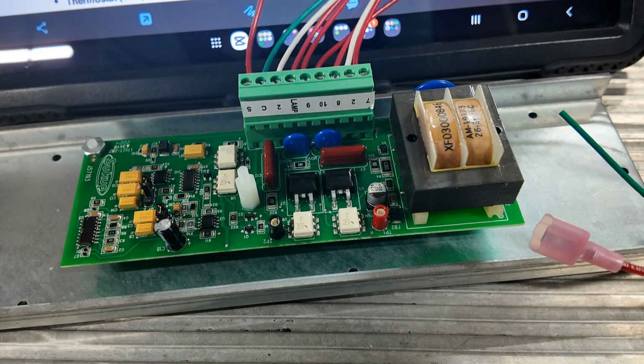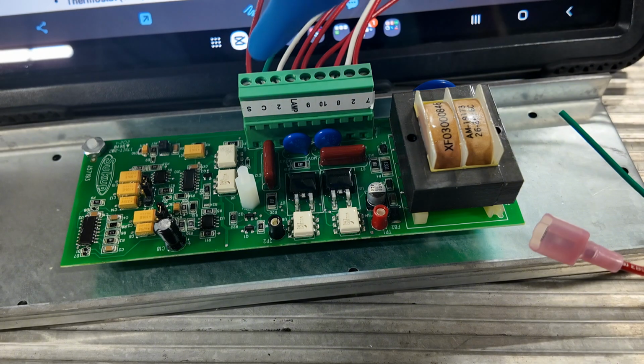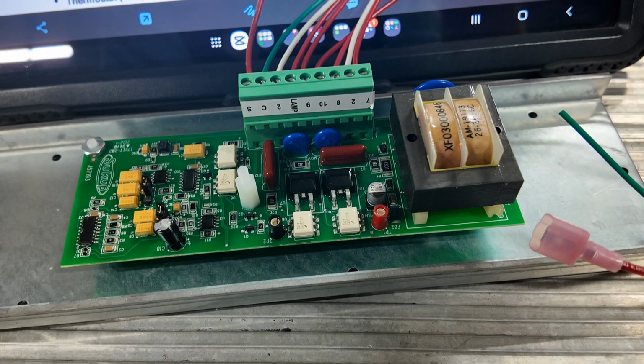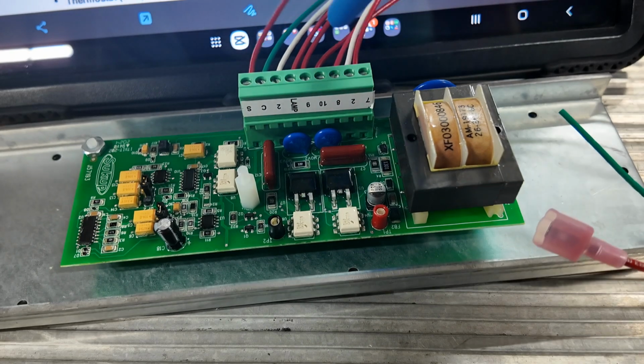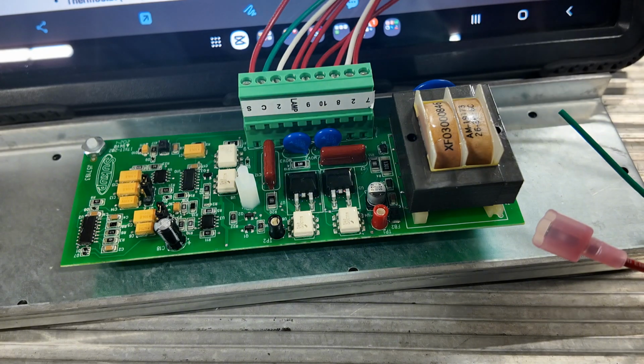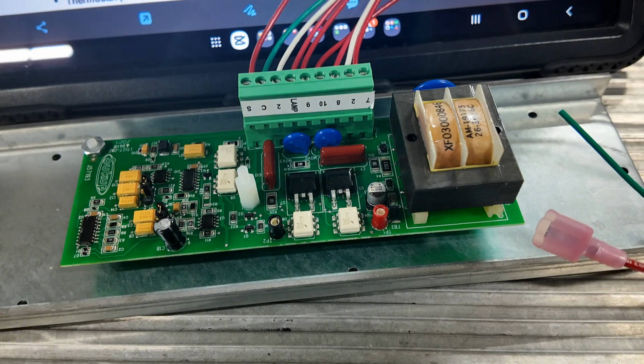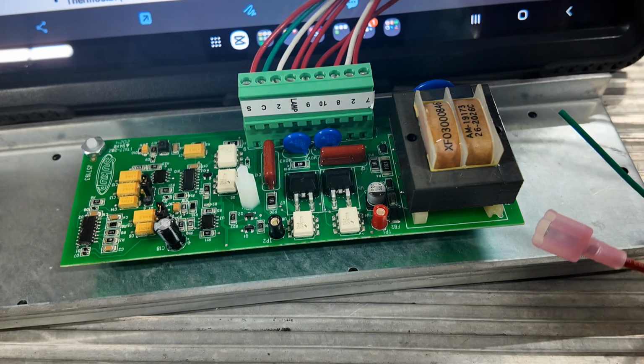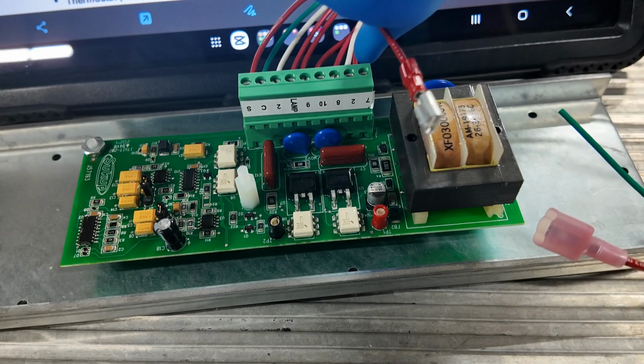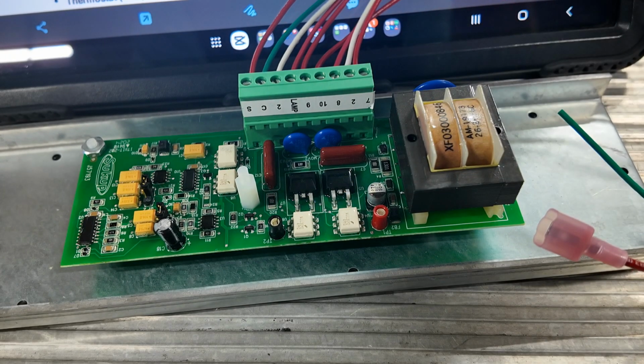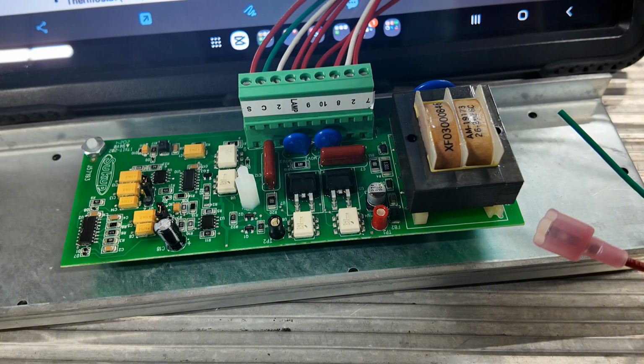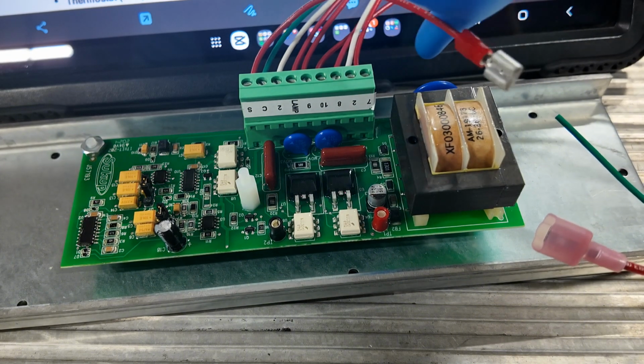This board monitors flame. So it puts electric into a rod that sticks in the burner, and when the flame touches the rod, it draws amps from the rod to the ground, and the board monitors the milliamps of draw. I believe it's milliamps. On the voltage tester, it's UA.